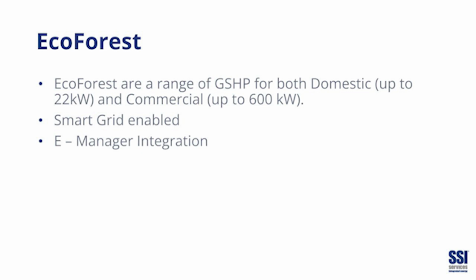So, EcoForest: up to 22 kilowatts for domestic, up to 600 for commercial, smart grid enabled, with e-manager integration. Smart grid enabled means the heat pump controller can receive a ramp up or ramp down signal, generally from the DNO supplier, saying we've got excess energy at the moment, ramp up, or we're short of energy, ramp down. If they ramp up, you can lift the temperatures of your thermal stores and domestic hot water; if you ramp down, you can reduce them while maintaining minimum temperatures.